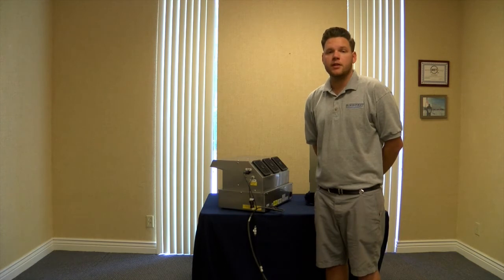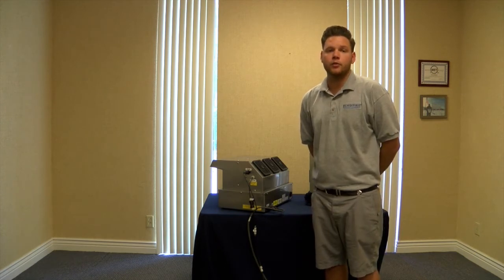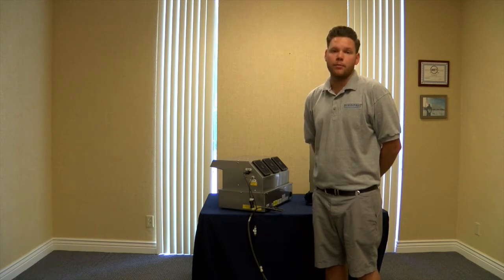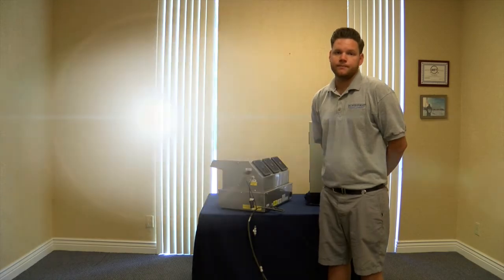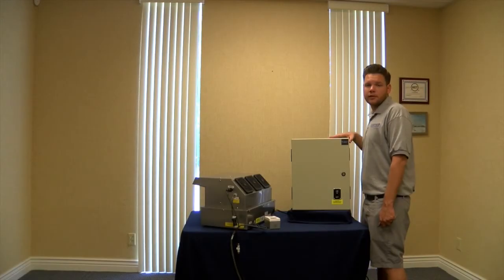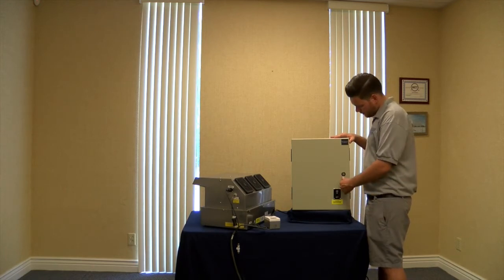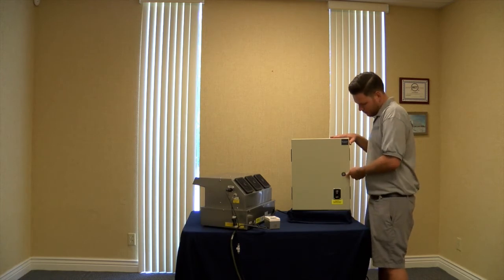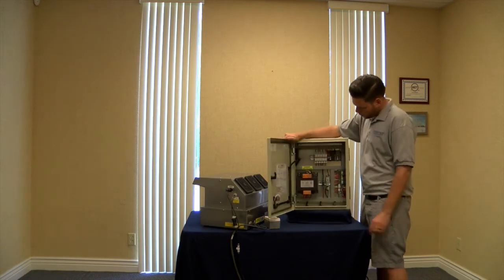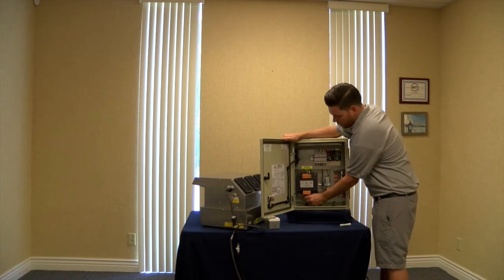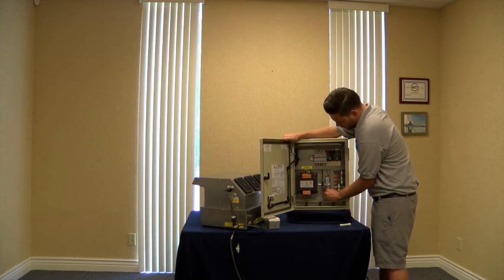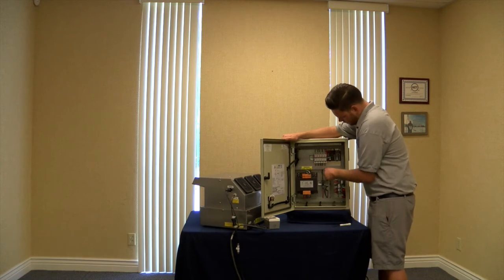Once you have done this, then you are ready to plug your control panel into the wall with the supplied 120 volt power plug. Before plugging in your 120 volt power plug, you're going to want to open the unit and check for any loose connections. Open it up and simply go in and pull on any wires to try and find any loose connection points.